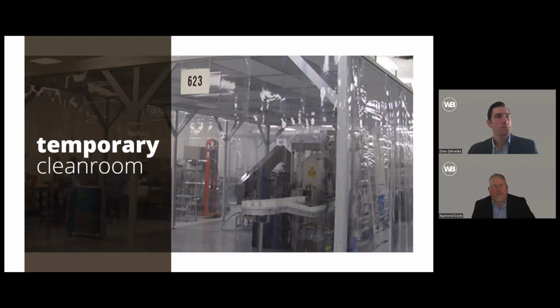The first one we'll talk about is a temporary clean room, and it is exactly what it sounds like. You could tilt up a ceiling with a couple posts and put HEPA filters and a light or two in there and get to a clean room classification that could meet the requirement of the science inside the tent. It just recirculates back underneath the curtain at the floor, equivalent to, say, a non-unidirectional low wall return. And it just goes back to the ambient environment in the space that it's in.